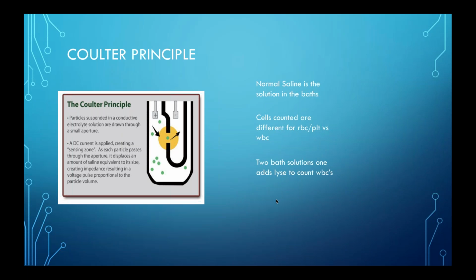WBCs are larger than the RBCs. In this bath, the green dots represent cells in general. But let's say this is an RBC bath. The RBC bath has the white cells in it and also the platelets, so what it measures in the RBC bath is everything. The reason is that RBCs are measured in the millions. A normal count for an RBC would be 4.2 to 5.8 million per CCM, and that's how many cells are being counted every 4 seconds.